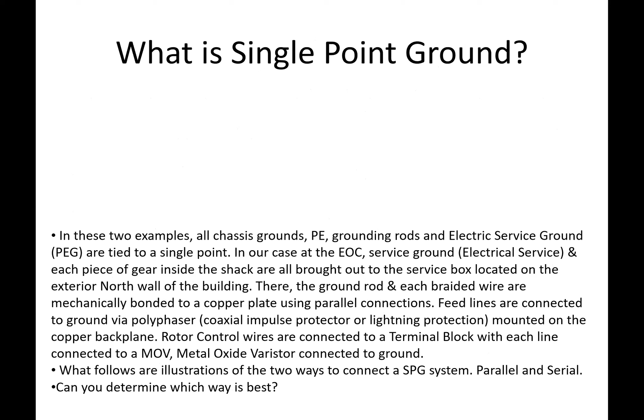What is single point ground? In these examples, all chassis grounds, protective earth, grounding rods, and electric service ground, or PEG, are tied to a single point. In our case at the EOC at Hope Hill Road, the service ground, which is the electrical service, and each piece of gear inside the shack, are all brought out to the service box located on the exterior north wall of the building.